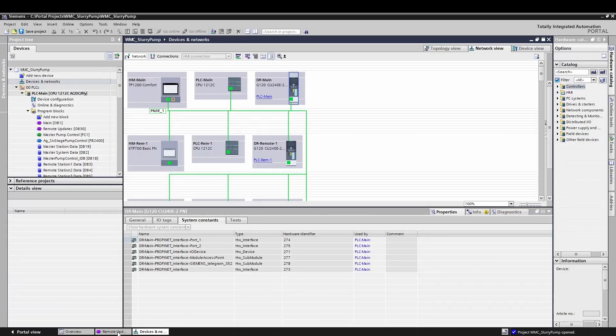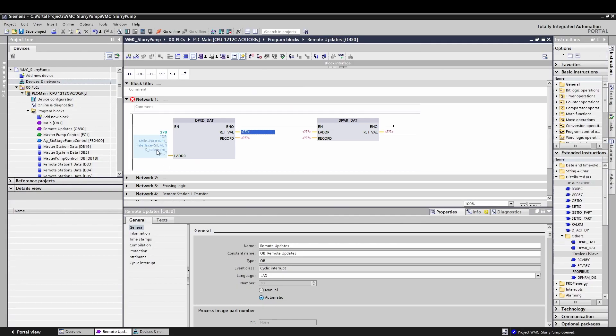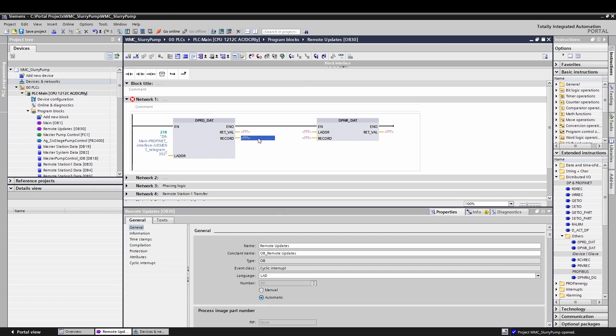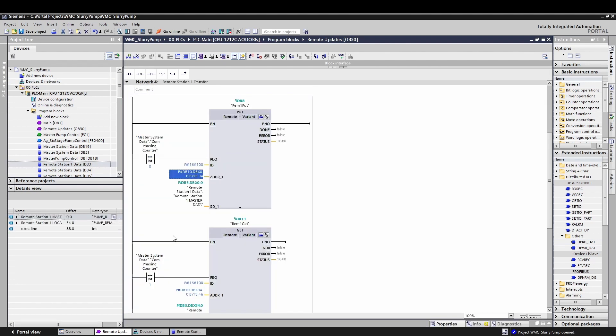Now that you have the L address parameter set, let's determine how to set the record parameter. This can be a bit tricky because you have to use a pointer to the starting address of the record and then the number of bytes that are being transferred. Now if you're unsure about how many bytes you are trying to send, there are a couple little tricks that I'll show you here.